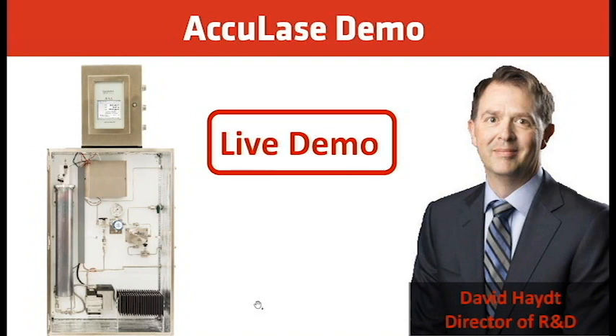The other thing that can happen with that oily type of stuff is that it can absorb, and it can also desorb. If you have a pressure drop or a change in temperature, it can also desorb H2S, so it might show up as a false positive in your analyzer as well. So that's really the importance of keeping the sample conditioning system free of liquids like that. It is very important to try to eliminate those types of false readings, either high or low, that you can get from your sample conditioning.